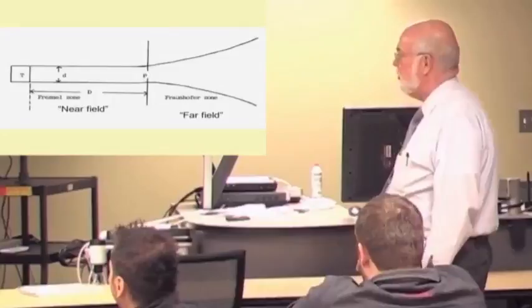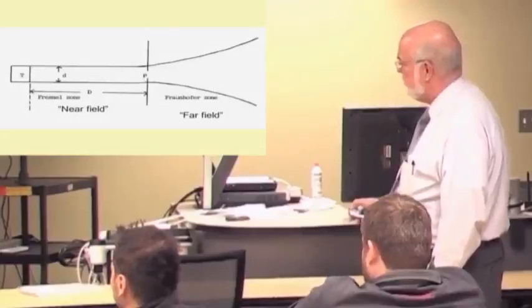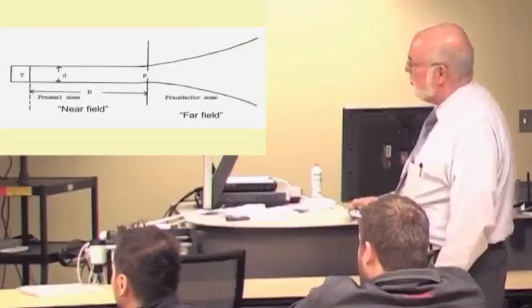Well, the near field is important to us because all of our best focus and the ability to introduce a focal point has to occur in this area. This area gets longer the bigger the transducer and the higher the frequency.